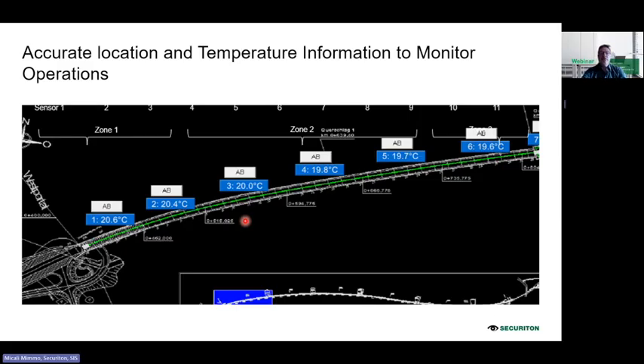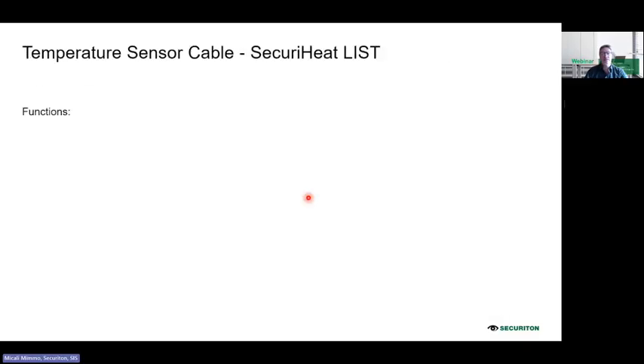Then all the sensors are reporting their temperature if they are connected by TCP Modbus to the SCADA system, and accurate information. The operator will see here, like on this graphic, sensor number 1, sensor number 2, number 3. You see the exact temperature. Remember, with the resolution of 0.1 degrees. So the operator can really see what kind of temperature he has in different sectors. And this may be helpful because sometimes he has to slow down the ventilator, or if the temperatures are very high in some sectors, he can also increase the velocity. But this is information which is very important, because if you see that in one sector we have a high temperature, he may switch to the camera, he may also look at other devices and see what happened or why we have such a temperature increase in a different sector.